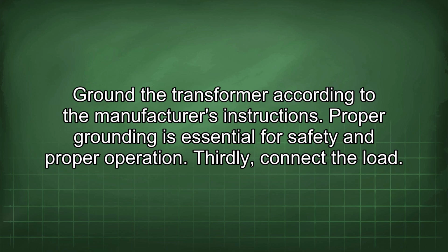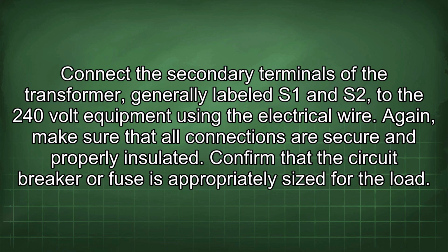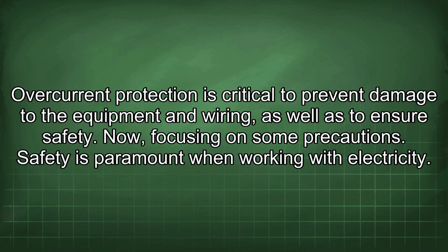Thirdly, connect the load. Connect the secondary terminals of the transformer, generally labeled S1 and S2, to the 240-volt equipment using the electrical wire. Again, make sure that all connections are secure and properly insulated. Confirm that the circuit breaker or fuse is appropriately sized for the load. Overcurrent protection is critical to prevent damage to the equipment and wiring, as well as to ensure safety.